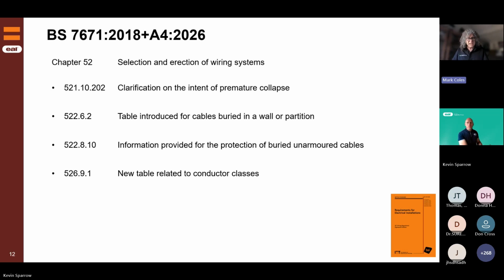So that was that one. On to 522.8.10, information provided for the protection of buried unarmoured cables. What this is about — if you look at that regulation, what's gone into the note is the particular rating for the duct and how impervious it is to weight and impact. 522.8.10, and this is the compression rating: N750. 750 is the rating in newtons that the ducting should be able to withstand. There are other ratings of ducting you can get which are less reliable, less strong, for want of a better expression. So 750 is the type that's gone into that.